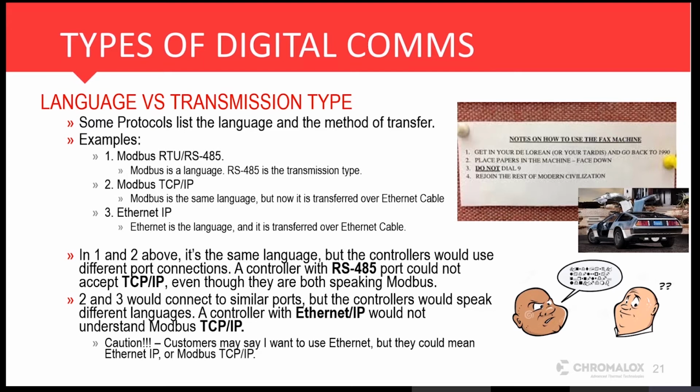So when we talk about the digital communications, you're often going to see it laid out in a language and a transmission type. So I have a couple of examples here. Modbus RTU RS-485 is a common one we see. In that case, Modbus RTU is the language that's being talked between the devices, and RS-485 is the transmission type, or the connection or the cable type.